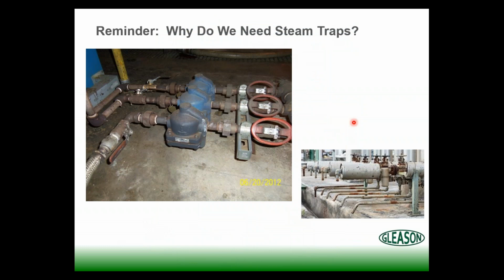So why do we need steam traps? I've heard it said, because maintenance people need something to do. Well, that's not exactly right. We need steam traps to trap steam in and to get everything else out of the system that we don't want, like condensate or water and air and other non-condensable gases. So the only thing we ever want in a steam system is steam. Traps help us do that.